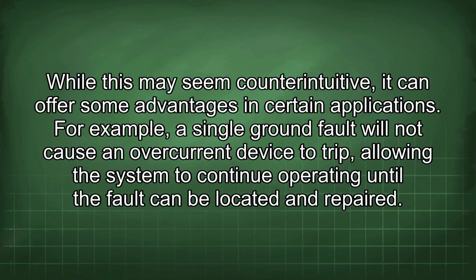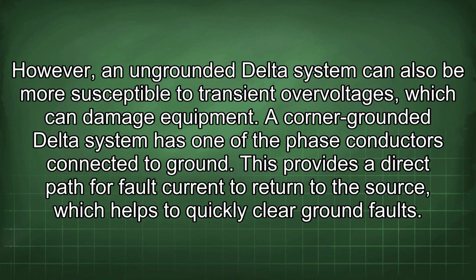For example, a single ground fault will not cause an overcurrent device to trip, allowing the system to continue operating until the fault can be located and repaired. However, an ungrounded delta system can also be more susceptible to transient overvoltages, which can damage equipment.